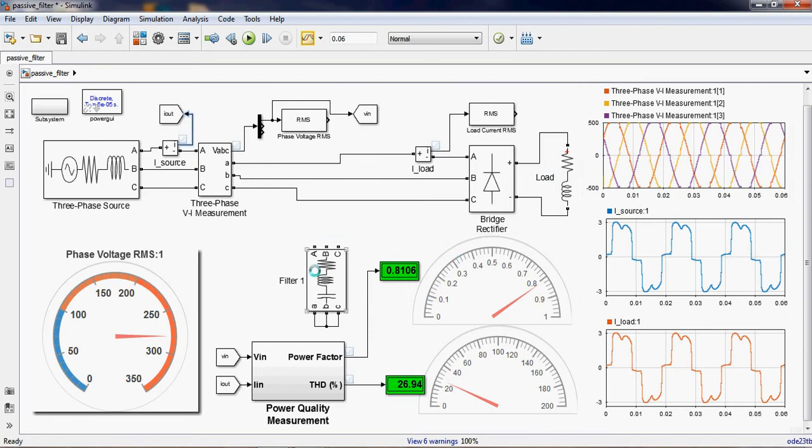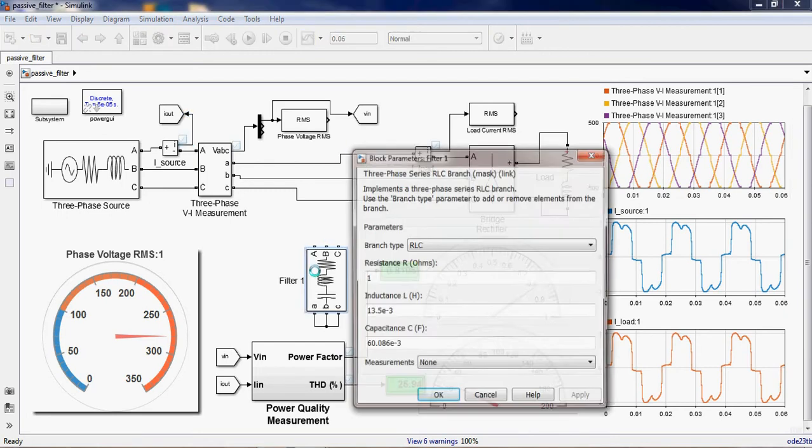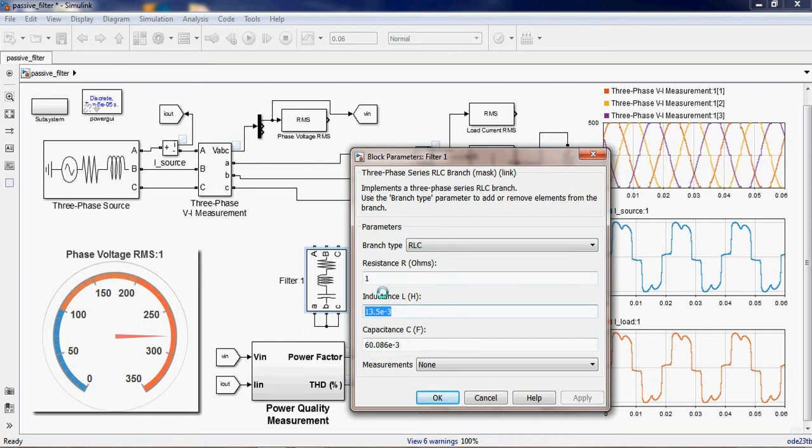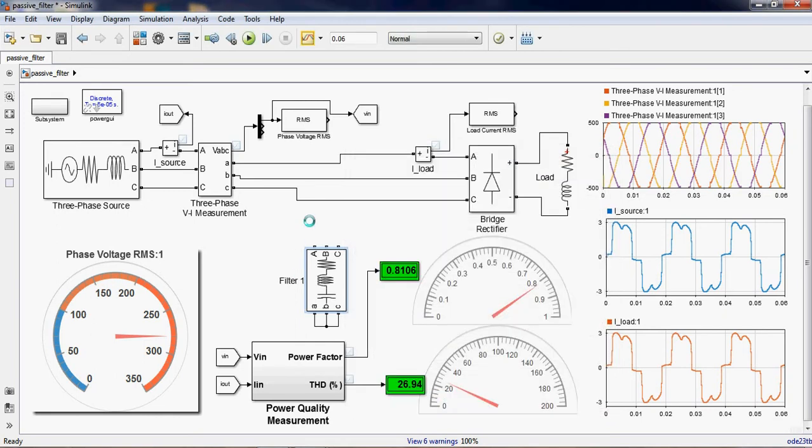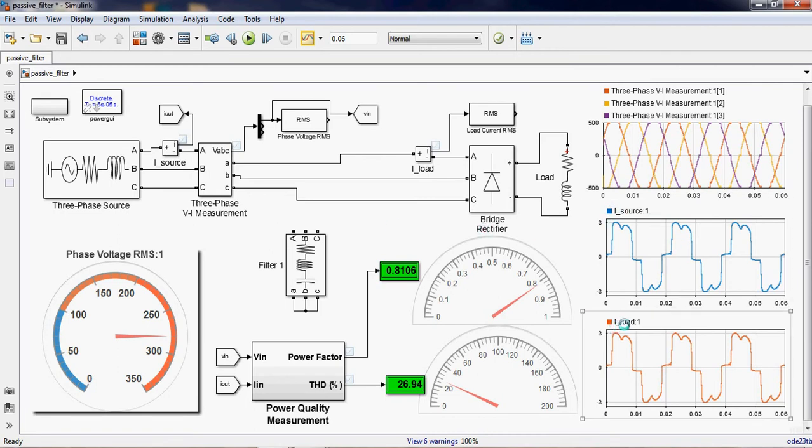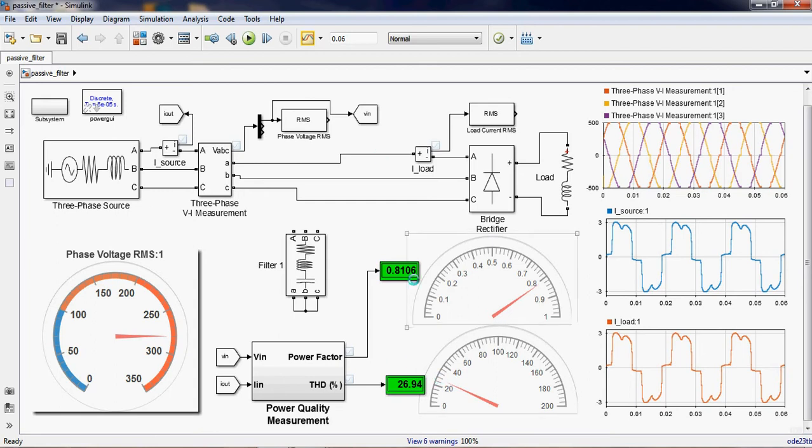Now this is the filter and I have calculated the values of filter according to my values, resistance, inductance, and capacitance. This is the passive filter as we earlier discussed about the theory. Now without the filter you can see here the source current and load current, very similar distorted line current, and THD is also followed, 26.94 percentage.